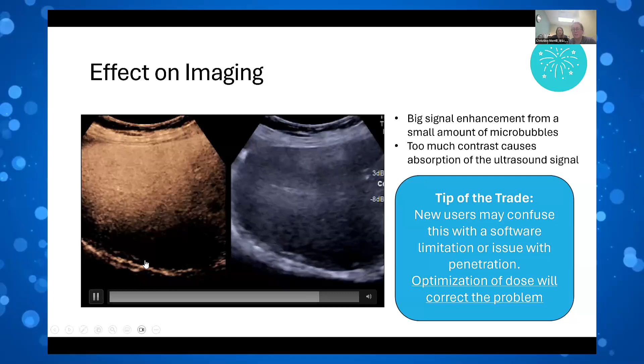Remember that we want to try and get microbubble imaging from the near field to the far field. Well, you can see in the far field of the liver here, all we get is a dark or a black signal, and this is caused by absorption of the sound beam from too many bubbles. So this is a tip of the trade, and we've certainly done this here. New users may confuse this with a software limitation or an issue with penetration. It is not. Optimization of dose will correct the problem. And I can't tell you how many times we've seen this, or even scanning for a longer duration of time. Once these microbubbles are destroyed, you'll start to see the back of the liver.